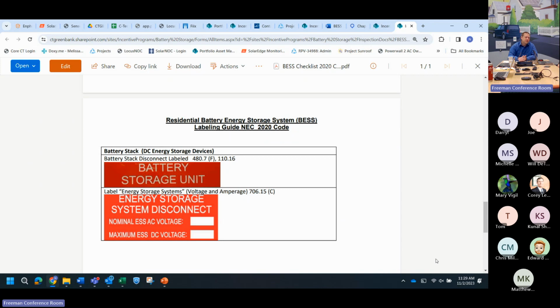Because it's just not that helpful, but it is code. Your AC voltage is going to be 120 volts almost certainly, or 240, depending on the unit. And the DC voltage in the box, that's usually on the label. So it's there if somebody wants it anyway, but there's a sticker that needs to go up in the front that has that. For those of you who want to go to PV Labels or one of those other websites, this is what the label looks like.